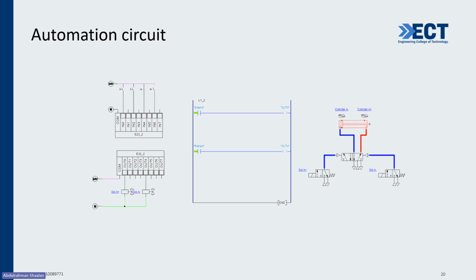What you can see here is a very basic example of ladder logic. You have an input signal to extend the cylinder, and as an output, that signal goes to the directional control valve to allow the extension to happen. Another rung is the retraction signal. Once that retraction signal is on and the connection is made, the output for retraction is on, and it retracts the cylinder by energizing the retraction position.